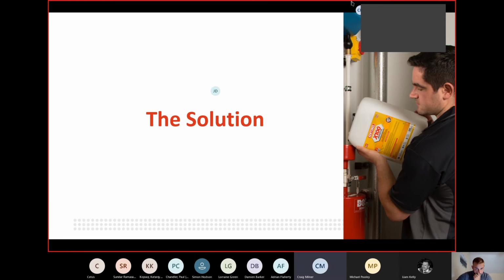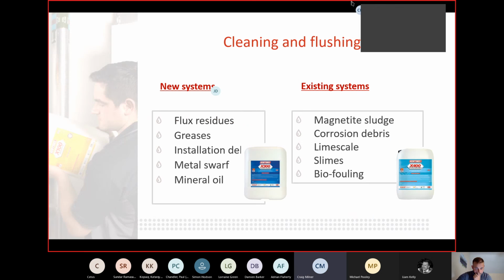Our part of the solution is adding the right chemicals. We have different cleaners for different types of systems. For new systems, you're looking at getting rid of any installation debris - when pipes are being stored, the merchants have grease or oil on there to protect them, and pumps, shafts and such like have greases in there. You need to remove all that. So we have something called X300, designed to lift mineral oil, swarf, and any installation debris.